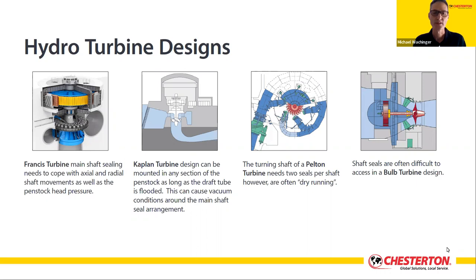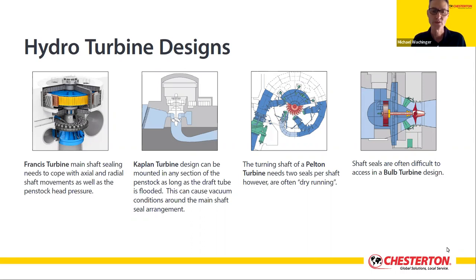In 1913, Victor Kaplan created a low head version of the Francis turbine by using an adjustable propeller-type blade to harness water flow energy. Runner blade pitch is hydraulically adjustable to help control water flow and turbine speed, along with wicket gates. It is best suited for low head, high flow applications. The design means the machine can be mounted at any section of a penstock as long as the draft tube is flooded; however, this can cause vacuum conditions around the main shaft sealing arrangement.